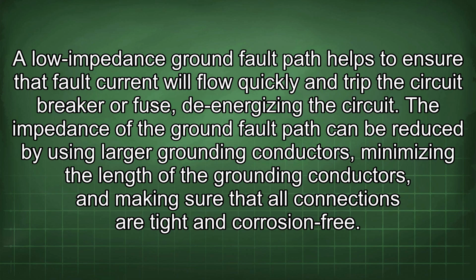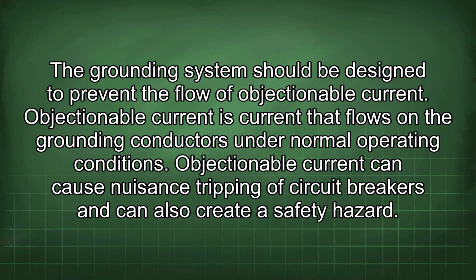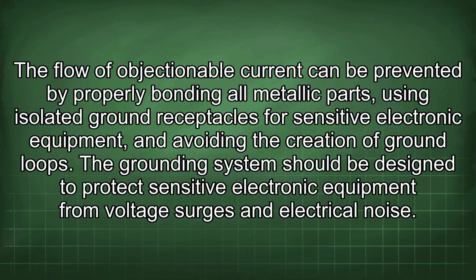The impedance of the ground fault path can be reduced by using larger grounding conductors, minimizing the length of the grounding conductors, and making sure that all connections are tight and corrosion-free. The grounding system should be designed to prevent the flow of objectionable current. Objectionable current is current that flows on the grounding conductors under normal operating conditions. Objectionable current can cause nuisance tripping of circuit breakers and can also create a safety hazard. The flow of objectionable current can be prevented by properly bonding all metallic parts, using isolated ground receptacles for sensitive electronic equipment, and avoiding the creation of ground loops.